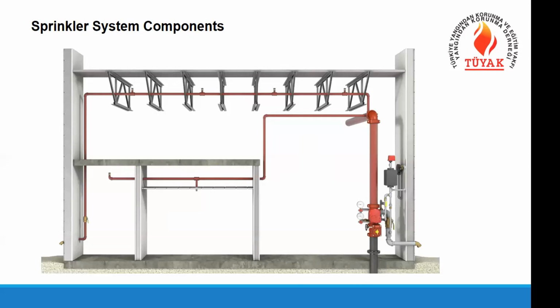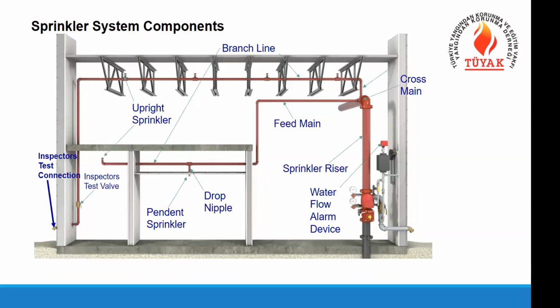And the system components of a sprinkler system consist of the alarm valves, the piping system, and the sprinklers on the different parts of the building. So you can see on the ceilings or sometimes on the wall the sprinkler heads. They are connected to each other with piping, and in the riser that we call the main pipe, we have an alarm valve. Why do we call it an alarm valve? This is a water flow alarm device. So when the water flows through this device, it gives an alarm, mechanical or electrical.